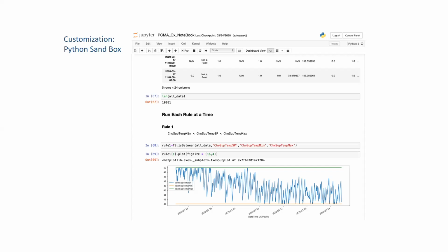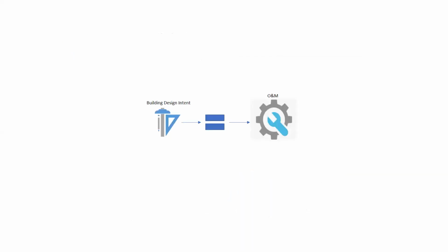This is an example where we had a brand new building, and I worked closely with our commissioning agent. He gave me the rules as an Excel spreadsheet, and I programmed them into the Jupyter notebook. This is showing rule number 1, where our commissioning agent wanted to make sure that the actual chilled water supply temperature set point stayed within the min and max range. We've used this heavily for this type of application, and for other applications, machine learning, anything else that requires customization and not an out-of-the-box solution. Next slide, please.